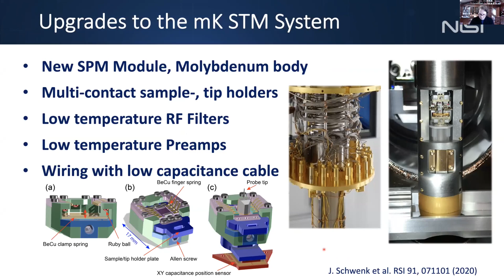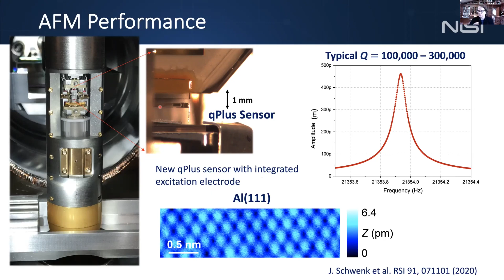So the AFM works as good as we hoped for. It can do atomic resolution mapping, it can do Kelvin probe mapping, as I'll show you later. We get Qs over 100K typically. Franz designed a new qPlus sensor for us because I didn't like the shaking piezos with an integrated electrode. So this is a nice qPlus sensor, which has four electrodes now, two for the AFM, one for the tip sensor, and a fourth one for the excitation electrode. So you can do all electric excitation.